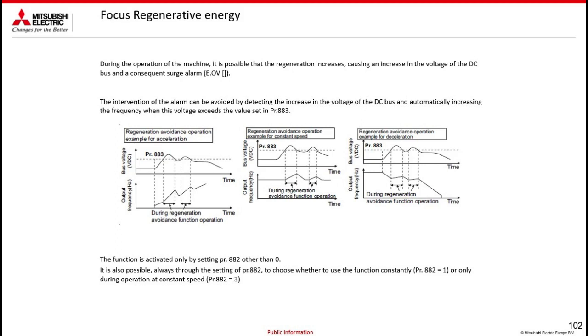What does regeneration avoidance do? It gives me a little bit of frequency, because if I'm pulling the load, I don't regenerate. If the load is pulling me, I go into this sort of regeneration. So I give a little bit of frequency so that the load doesn't pull me anymore, but I'm always pushing the load. Obviously, the DC bus voltage goes down below the limit value. So I try to brake again. It goes up again. I give a little bit of frequency so that it goes back below the threshold value. I try to brake again. It stays below. I brake. I stop. This function is very useful, because I can brake without disengaging the motor, without making an error.